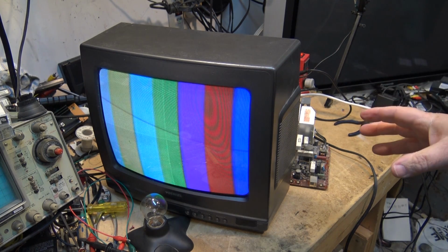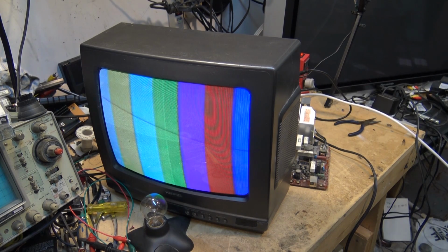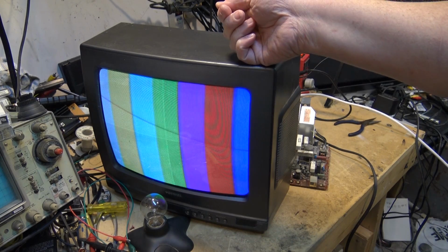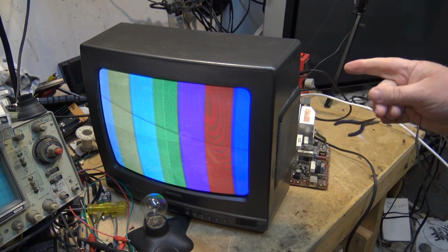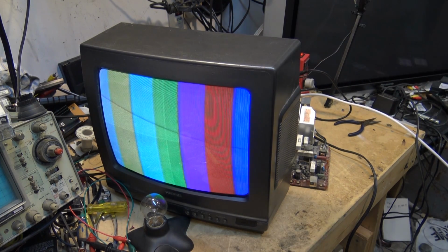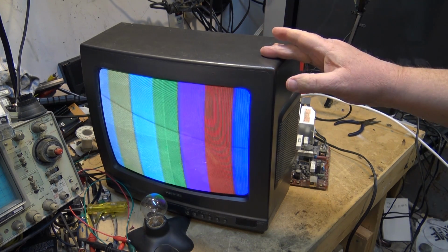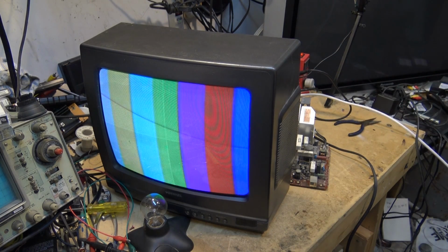Now, if you have an isolation transformer that's got a third ground prong on it, what you need to do is you need to remove that ground prong from the plug that you plug in. You need to remove that so that the transformer itself is floating free. And preferably, if it's got a three-prong outlet going that you would plug units under test into, remove the ground prong from that as well. You want no ground connection through that transformer or through its body. You want your transformer to be completely floating free so that either terminal can be pulled to ground. You want no reference from that secondary back to the utility ground or the utility neutral.